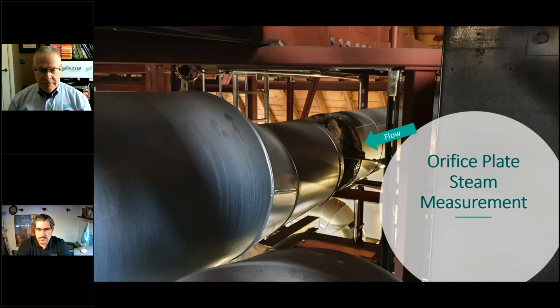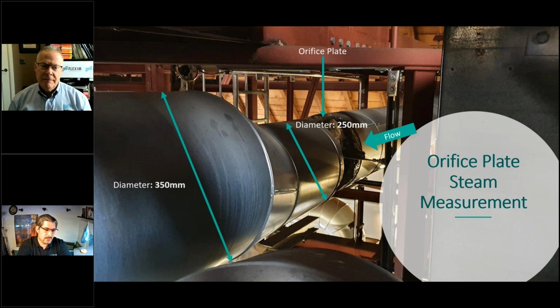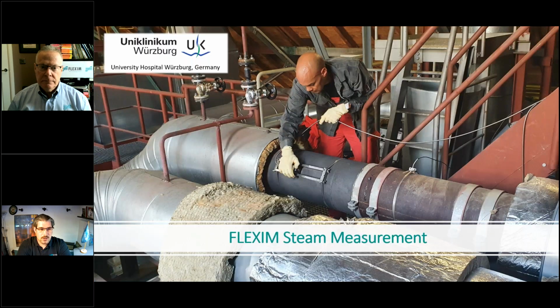Same situation, just from another perspective. You have the orifice plate, the smaller diameter, and then it goes back again to the large diameter of 350 millimeters. So I think the problem is obvious. If you're installing those kind of conventional meters, you have to handle those pipe diameter reductions, and this will give you just a bad time with your boiler efficiency. So yeah, let's propose a different solution.